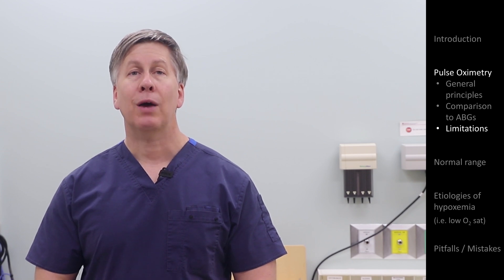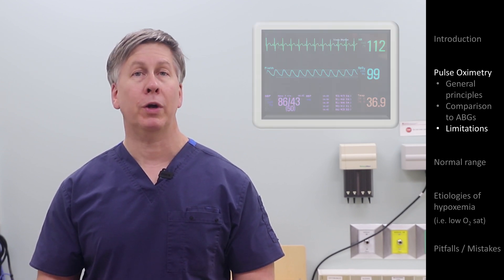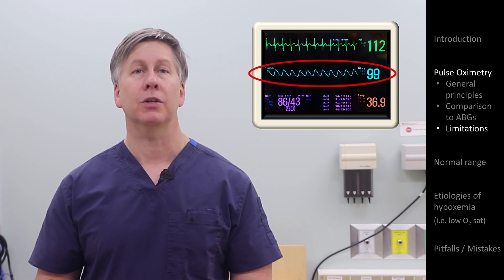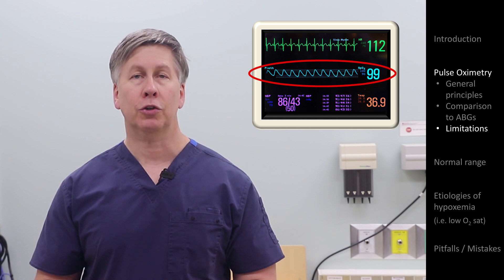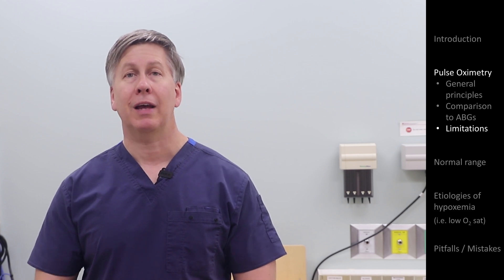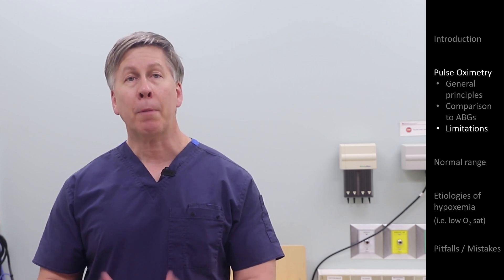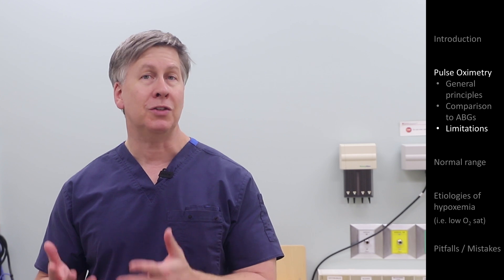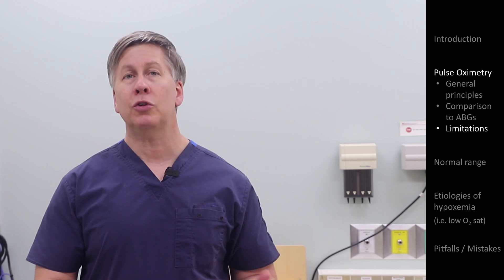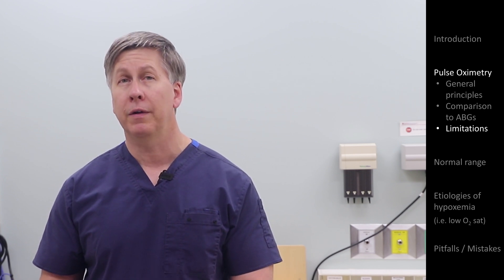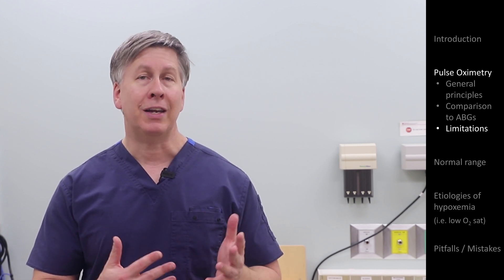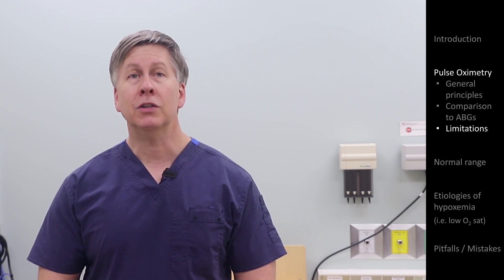On some devices, that waveform is visibly represented on a screen, from which you can determine whether it appears to represent the normal shape and rate of the arterial pulse. On other devices, the waveform is not represented, and the device is supposedly designed to simply not provide any number at all if it does not sense pulsatile flow. But unfortunately, sometimes these devices will still provide an O2 sat even when the signal for pulsatile flow is poor — and if the waveform is not displayed and you only see a number, you will not know it's inaccurate.